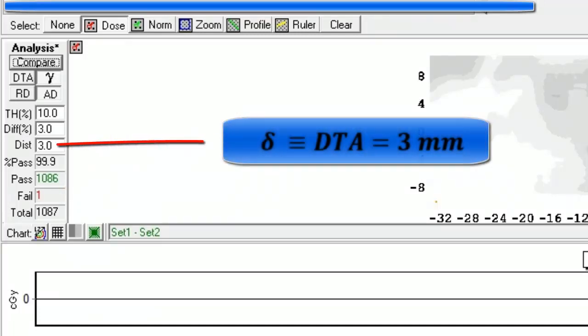Delta, which is known as distance to agreement or DTA, was 3 millimeters, and the height of our ellipsoid was 3%. The final result would be written like this: Gamma 3,3 equals to 99.9%.